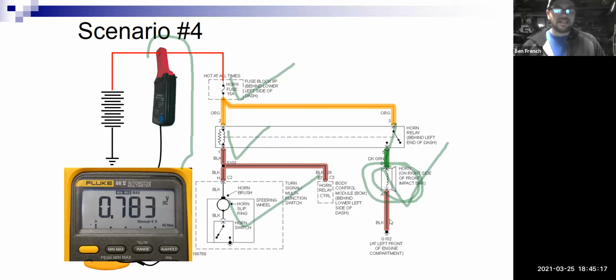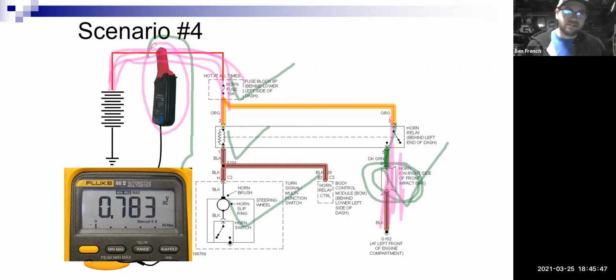Remember, let's say the horn was totally shorted out. I'm going to put my drawing tool back up, and let's say this horn was shorted out internally and we had 20 amps trying to flow through here. Well, remember, if my meter was hooked up in series, I would have just blown the fuse of my meter. I could have 20 amps flowing through this wire, and that's not going to damage this low amps probe, and it's not going to damage my meter either. So that's why I really like these low amps probes.